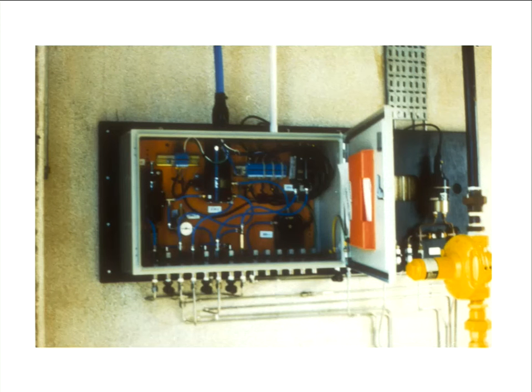So you don't want to keep firing it shut when it's not correct, but you want to be sure that it will close in. And you might have more than one level of pressure safety. You know, and typically they'll offer 3 or 4 different levels. First level might be a simple alarm. The next level might be start to try and control. The next level might be shut completely down, because we've failed.